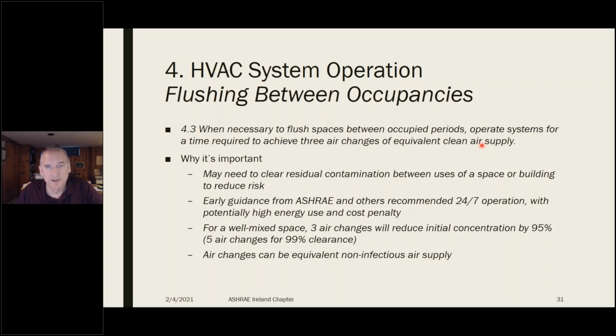If we can take credit for what filters and air cleaners are doing, we might have, instead of an hour of flushing with our outdoor air supply, 3 air changes per hour, this might take 20, 30 minutes. So it's important because in some cases we really do want to clear residual contamination. It's important because we need to be clear that our original 24/7 recommendation isn't supported anymore.